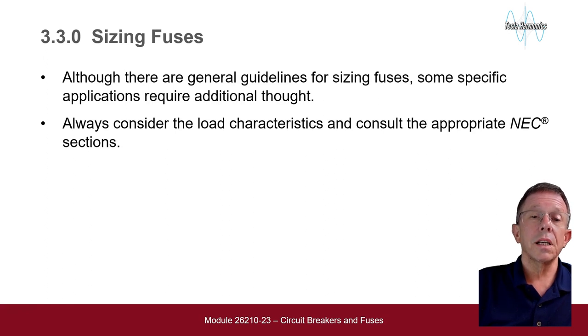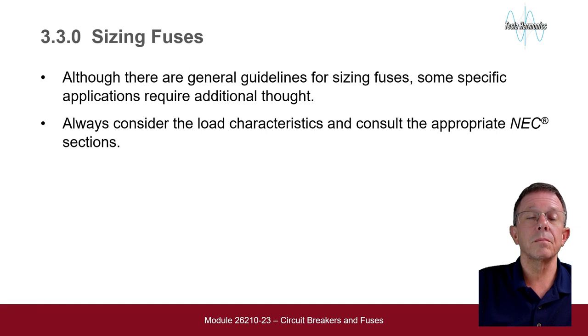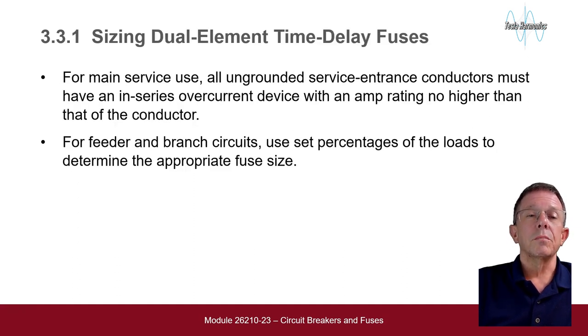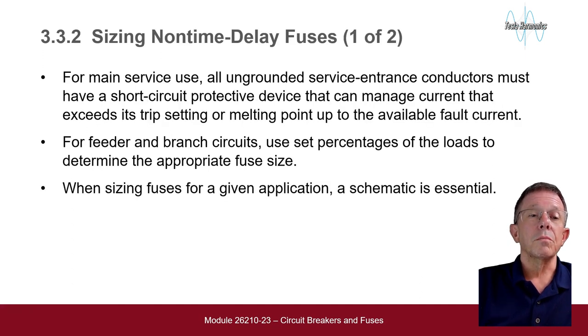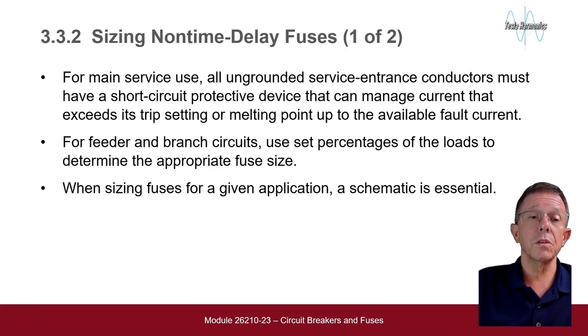Sizing Fuses. Although there are general guidelines for sizing fuses, some specific applications require additional thought. Always consider the load characteristics and consult the appropriate NEC sections. For sizing dual element time delay fuses, for main service use, all ungrounded service conductors must have an in-series overcurrent device with an ampere rating no higher than that of the conductor. For feeder and branch circuits, use set percentages of loads to determine the appropriate fuse size. For main service, the protective device must manage current that exceeds the melting point of the available fault current.